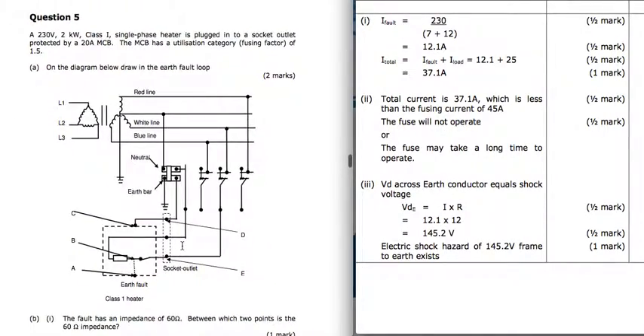Question 5. We've got a 230 volt, 2 kilowatt class 1 single phase heater plugged into a socket outlet. There's our socket outlet there. So there's our heater. There's our three phase supply, and it looks like we're coming off the white line there. So we're taking the white phase to the socket outlet. Would normally just go through the appliance like that, but we've got a fault going down here, back through the MEN link, back to the neutral.